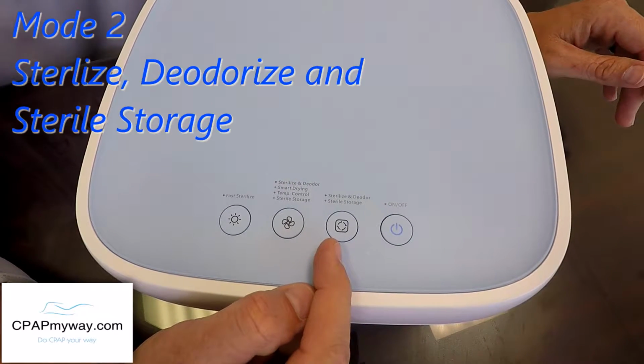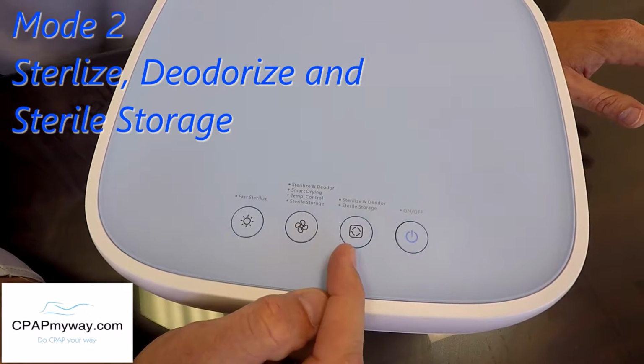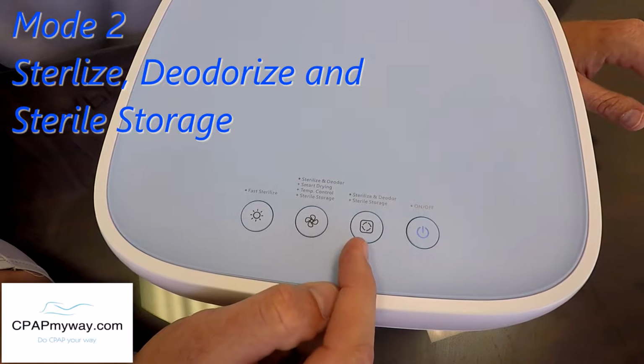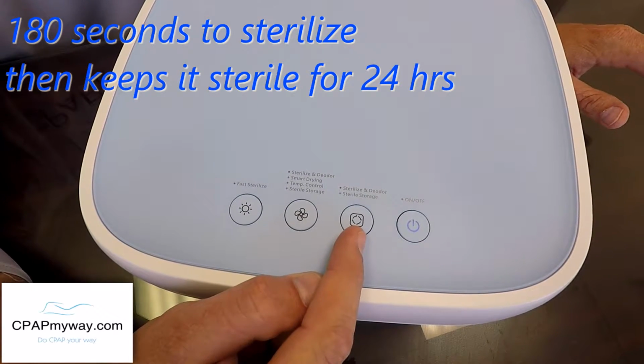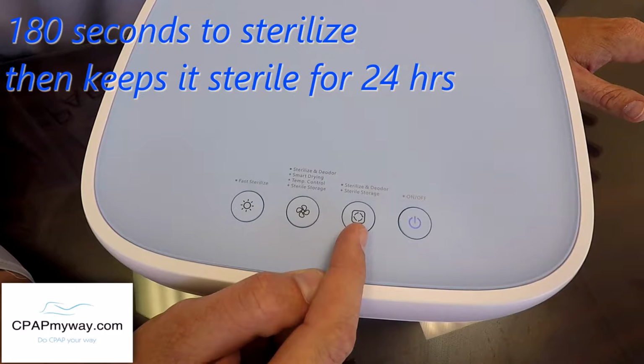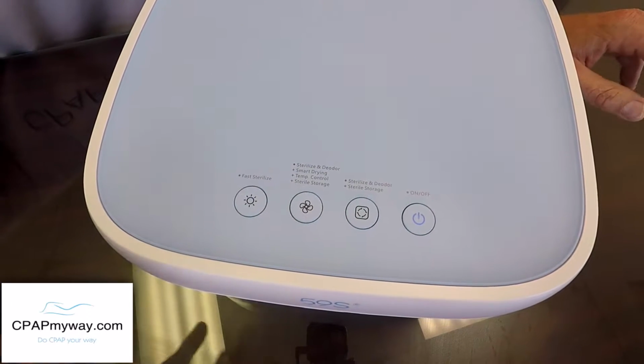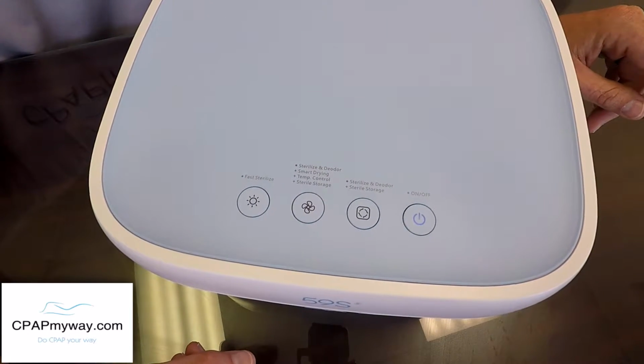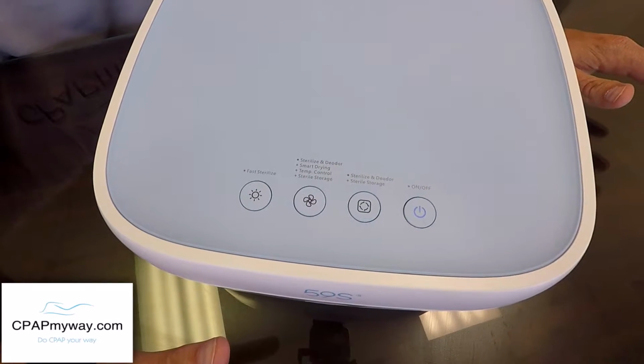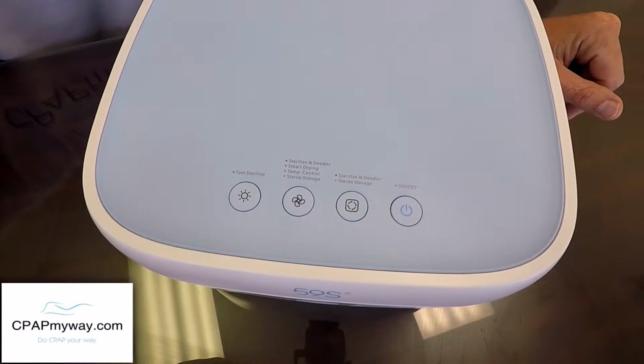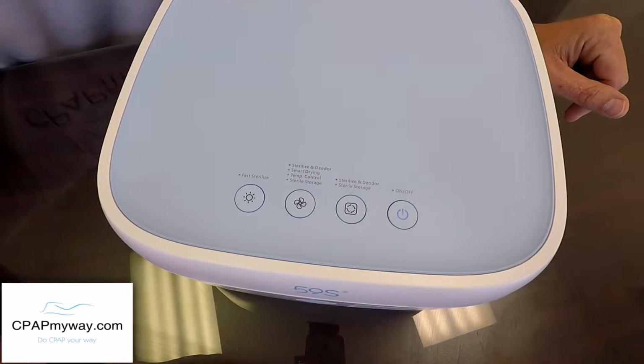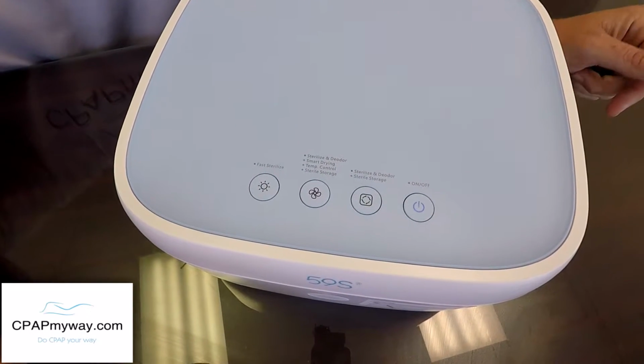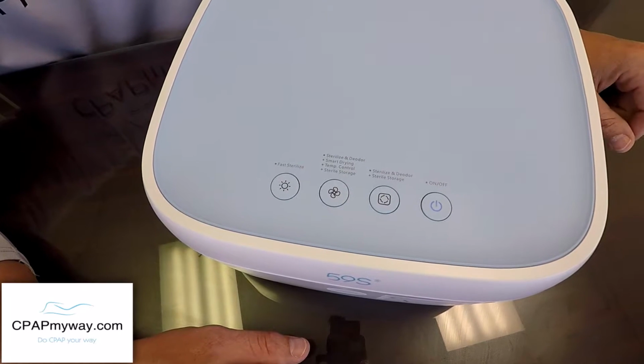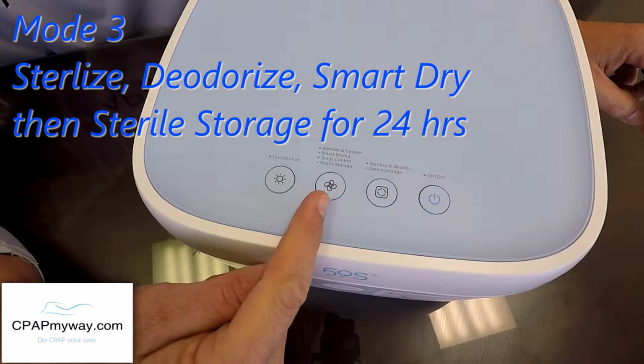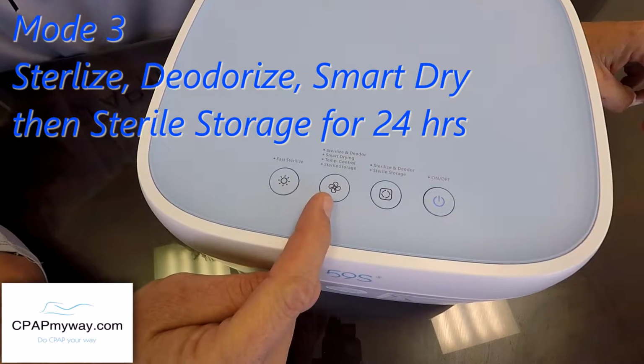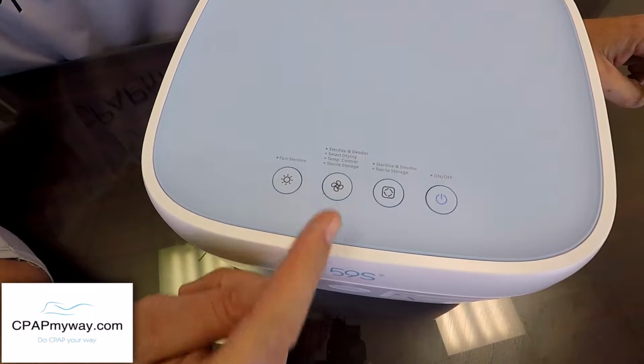Jumping over here, it's the sterilization, deodorization, and sterile storage. So if you select this, you're going to go through the 180 seconds of sterilization and deodorization. And then it's going to jump into a sterile storage environment where it will lightly run the UVC-LED bulbs and keep everything sterile for up to 24 hours, obviously in between CPAP usage or until you're going to use whatever's in there. The third option is the sterilization, deodorization, and smart dry.